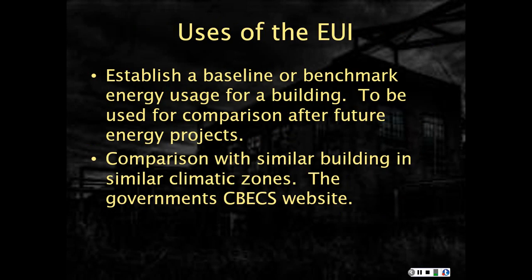Now, how is the Energy Utilization Index utilized? Basically, it establishes a baseline or benchmark energy usage for a building. What I want to do is take a year's worth of all utility billing and come up with some sort of number that equates to energy usage per square foot that I can use later on to compare after I do future energy projects.